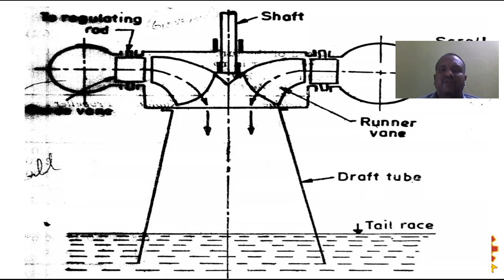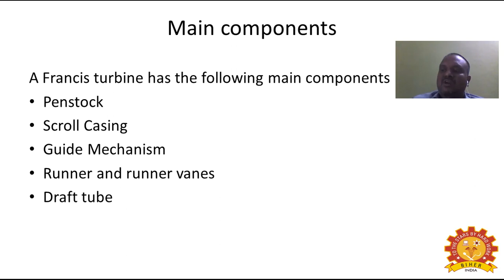These are the main components of the Francis turbine. A turbine in which the flow is directed radially inward and discharges axially is known as a Francis turbine. In the modern Francis turbine, water under pressure enters the runner in a radial direction towards the center and leaves the runner axially. The type of turbine with this mixed flow is a Francis turbine, or reaction turbine. The five main components are: penstock, spiral casing, guide mechanism, runner and draft tube.